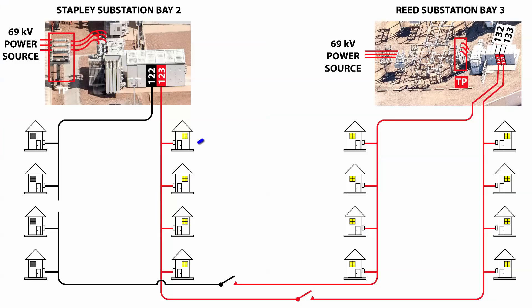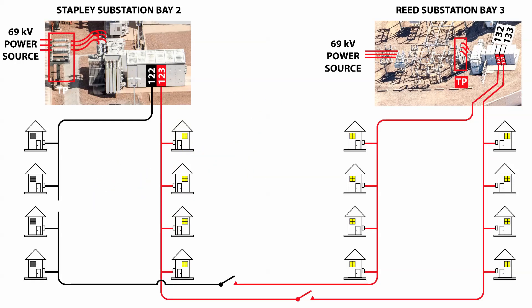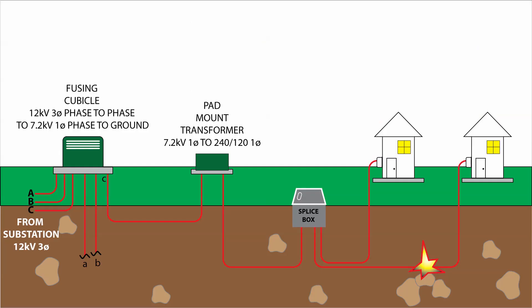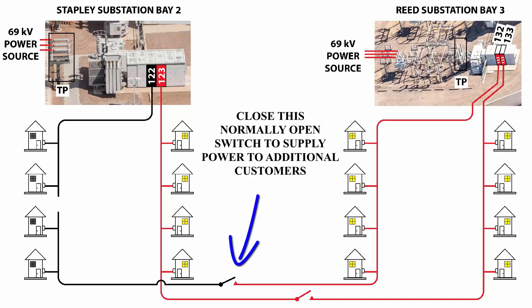After I know where the fault is, I isolate it. Isolating a fault means disconnecting the area of the fault from the rest of the power system — opening up disconnect switches or opening up circuits at 7.2 kV to 240 volt transformers creates air gaps which isolate the fault. Now coordinating with DOC, I close in the normal open, restoring power to the customers between the normal open and the fault.